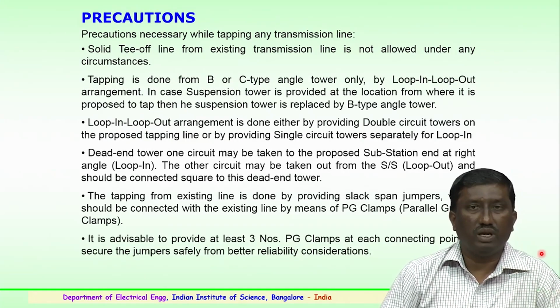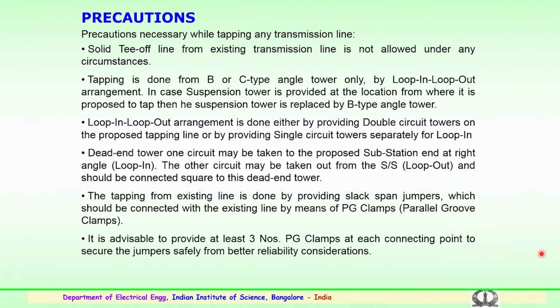Some precautions have to be taken while going in for the tapping of any existing transmission lines. A solid tee off line from the existing transmission line is not allowed under any circumstances. You cannot take the connections from the existing line with a solid tee off. So, tapping is done from either a B or a C type angle tower only, by the loop in or loop out arrangement as indicated earlier. In case a suspension tower exists at the location where the loop in loop out arrangement is to be done, then this existing suspension tower is to be replaced by a suitable B type angle tower.